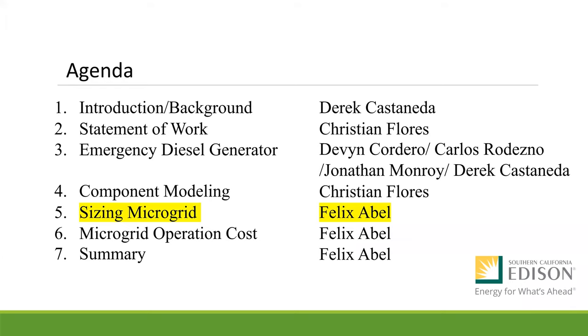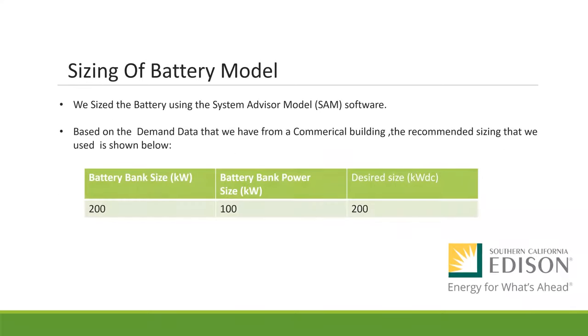I'll be passing it on to Felix Abel, where he's going to discuss sizing of the microgrid. Sizing of the microgrid is important to ensure that we have enough battery bank power and a big enough PV array size to meet our demand and also have resiliency in our microgrid system. We sized our battery using the system advisor model software from the National Renewable Energy Laboratory. Based on the demand data that we have from the commercial building, the recommended sizing that we used is shown below. Our battery bank size is 200 kilowatts, our battery bank power is 100 kilowatts, and our desired size for PV array is 200 kilowatts DC.